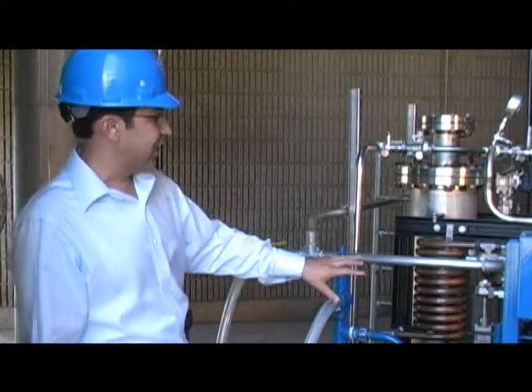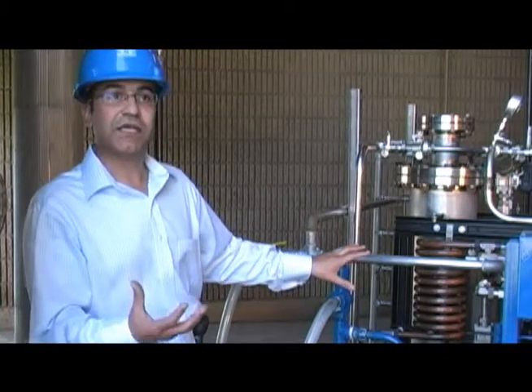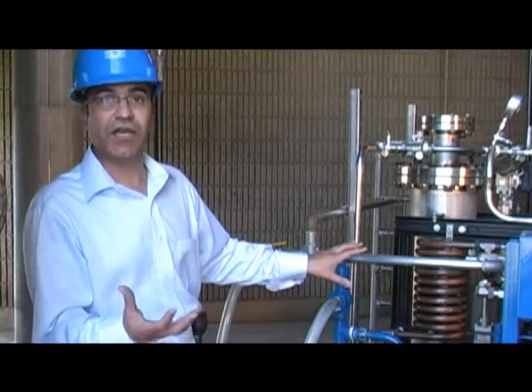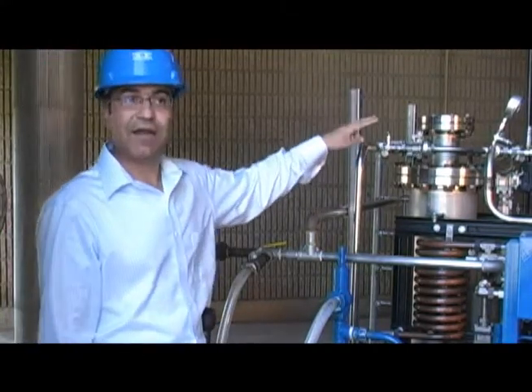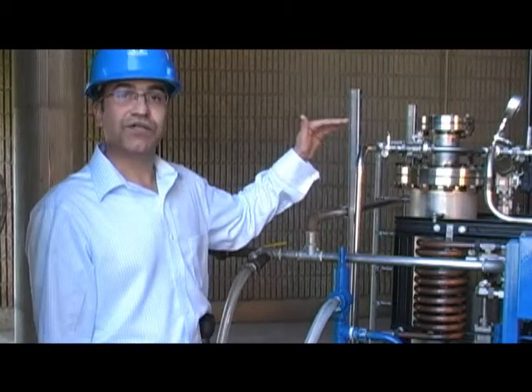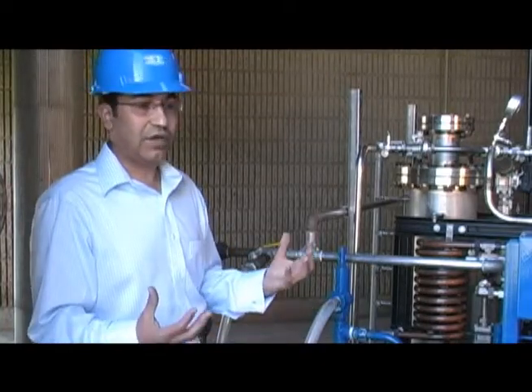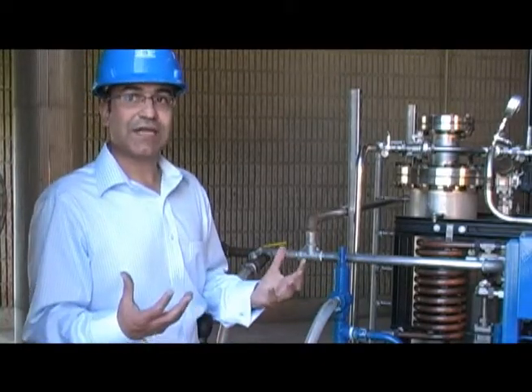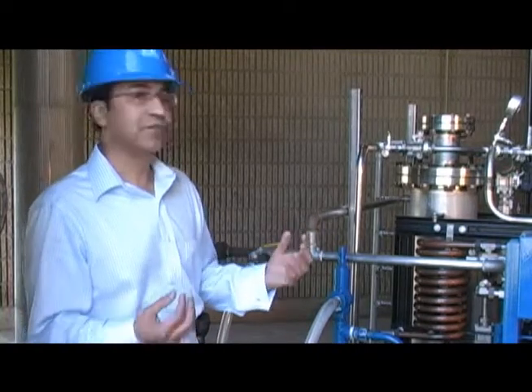From that, it goes again into the same plate heat exchanger, where it is reheated to 25 to 30 degrees centigrade, and from there it goes into two parallel siloxane removing vessels. Again here, the treated biogas enters from the bottom of the vessel. Currently we are testing two different types of silica gel. One is irregular and one is more spherical.